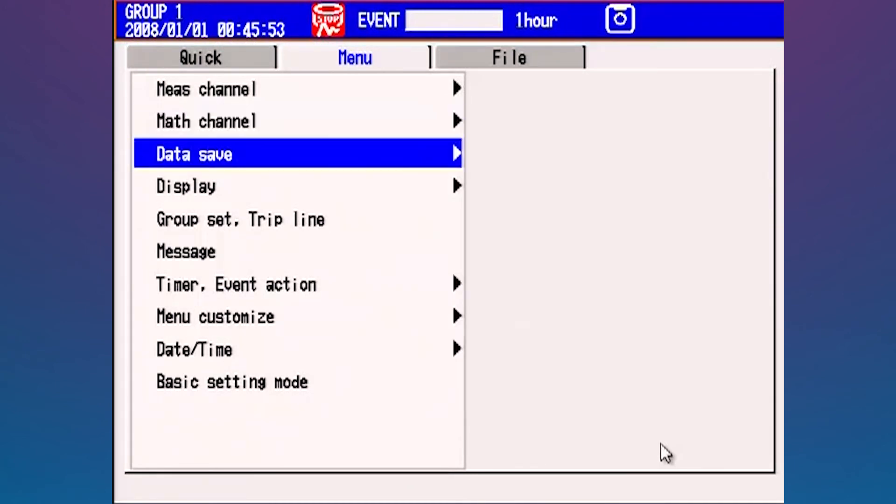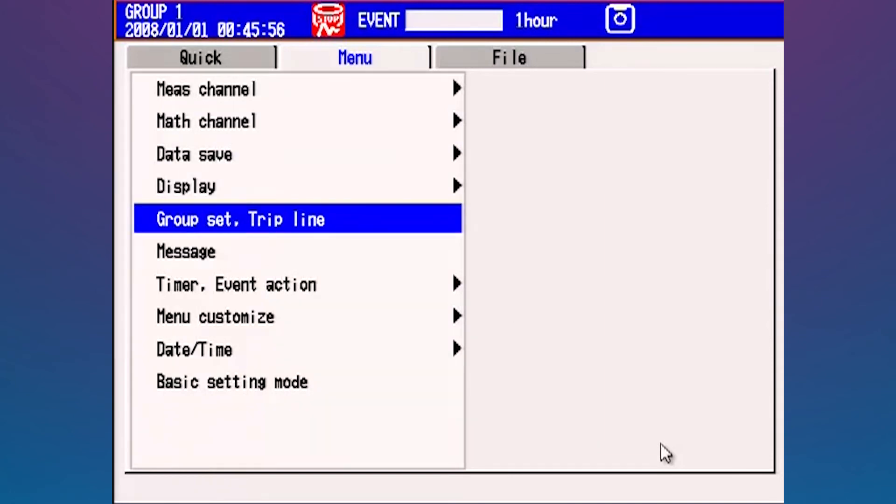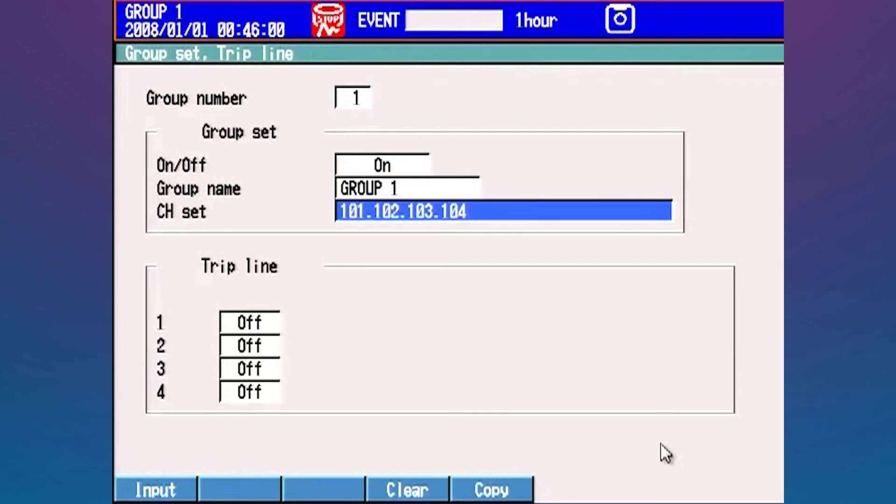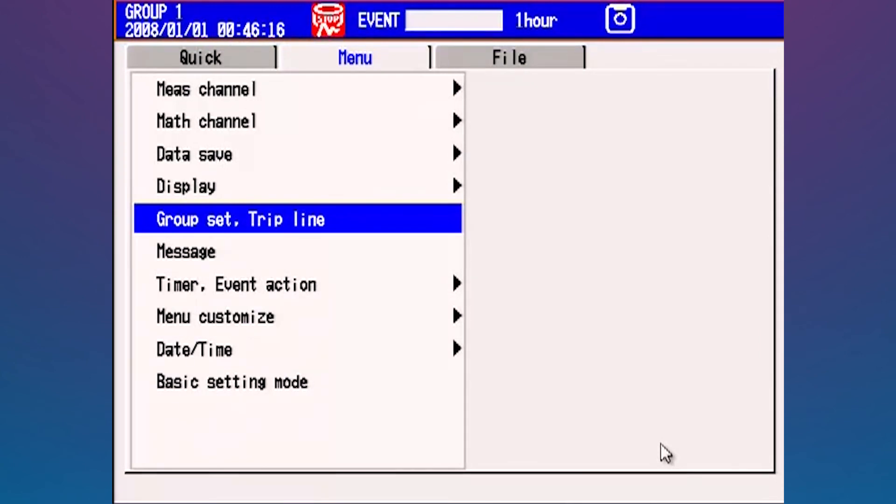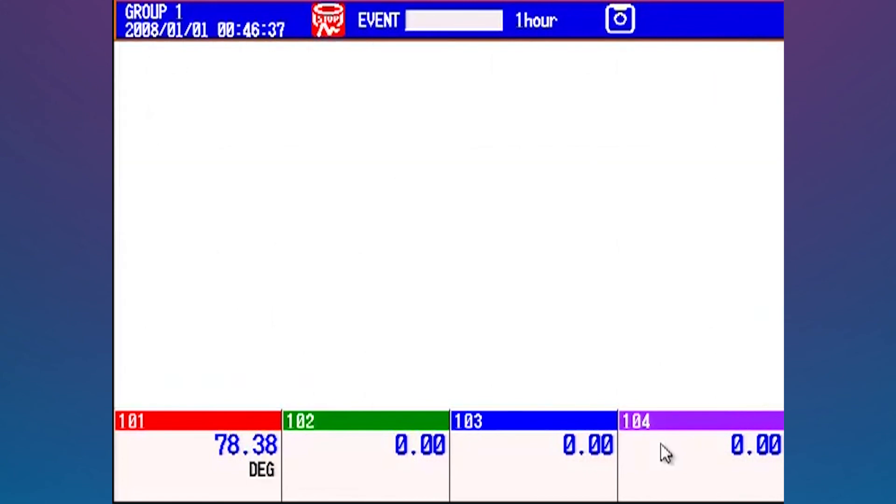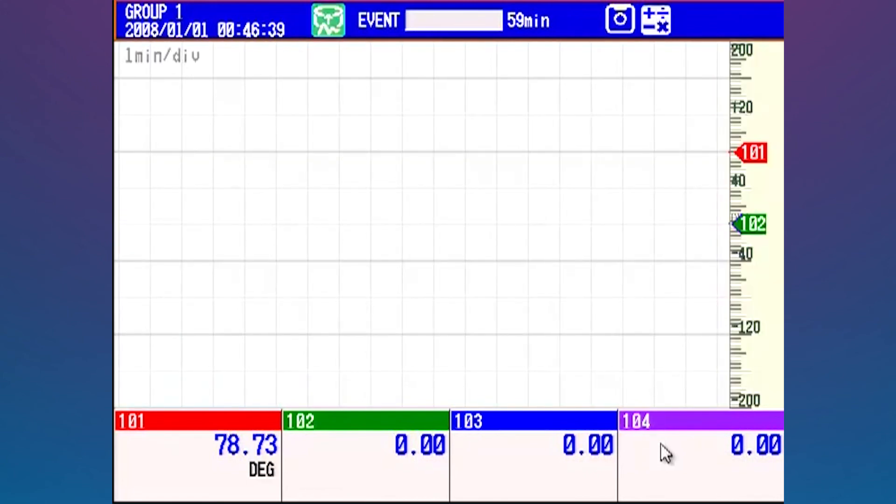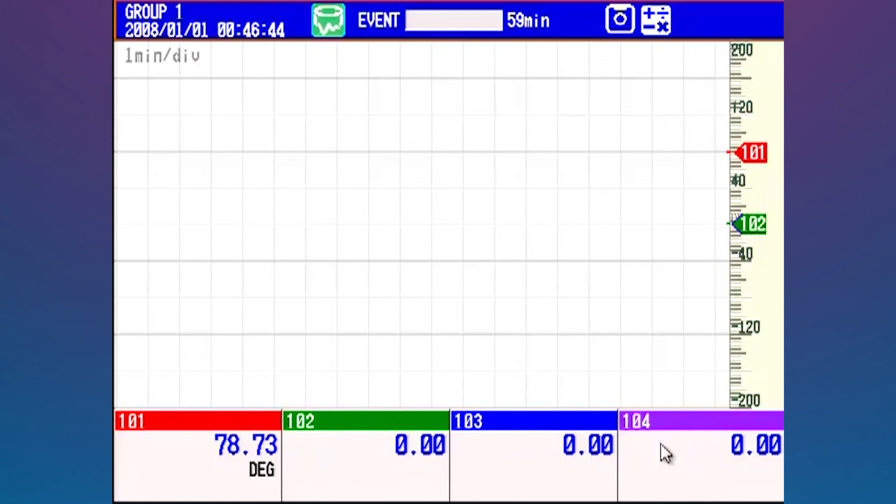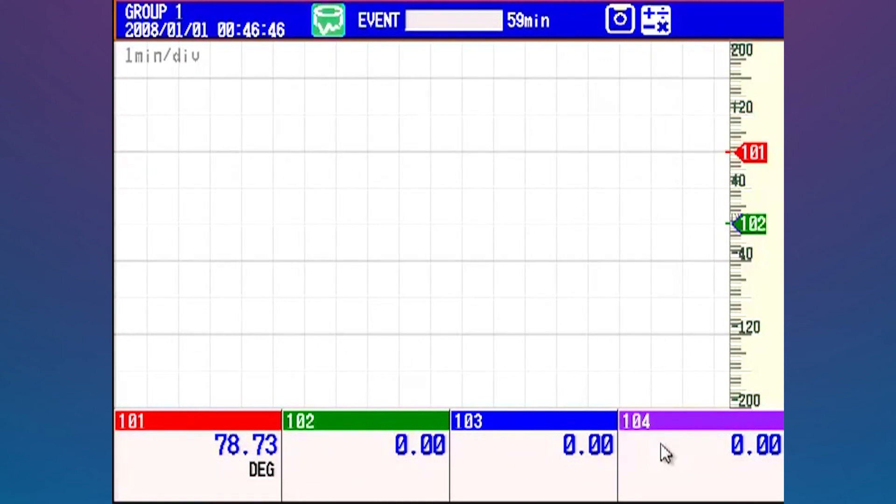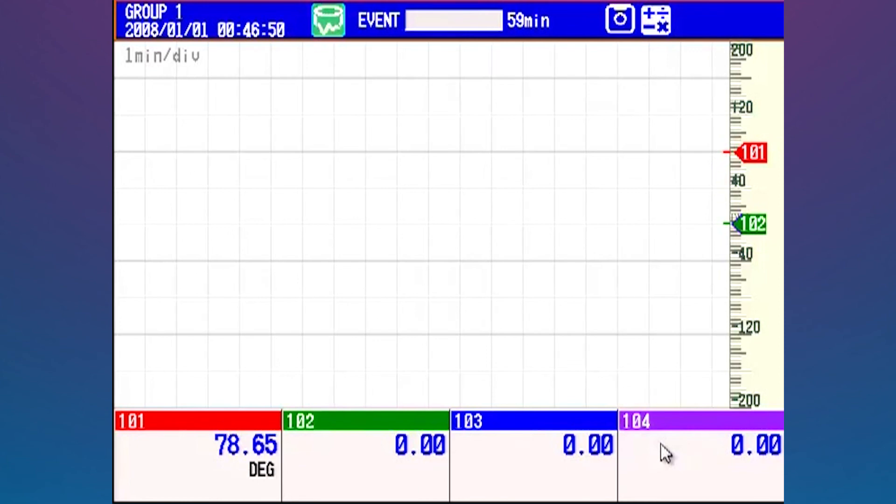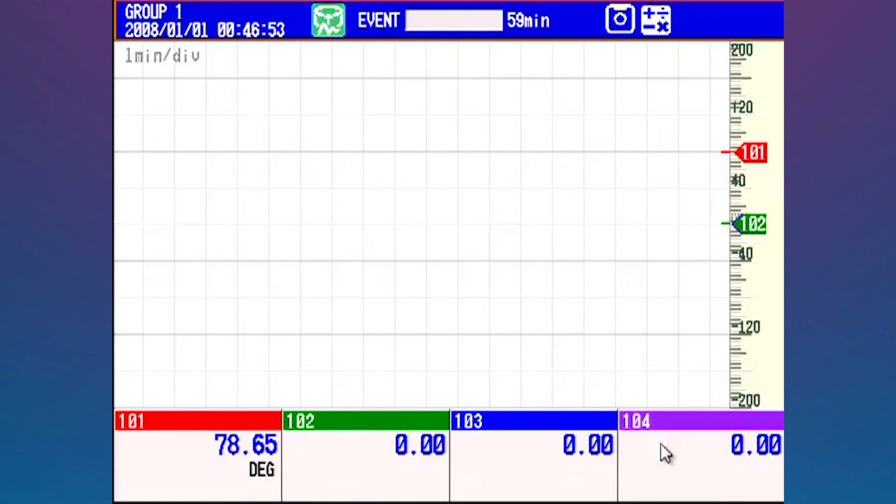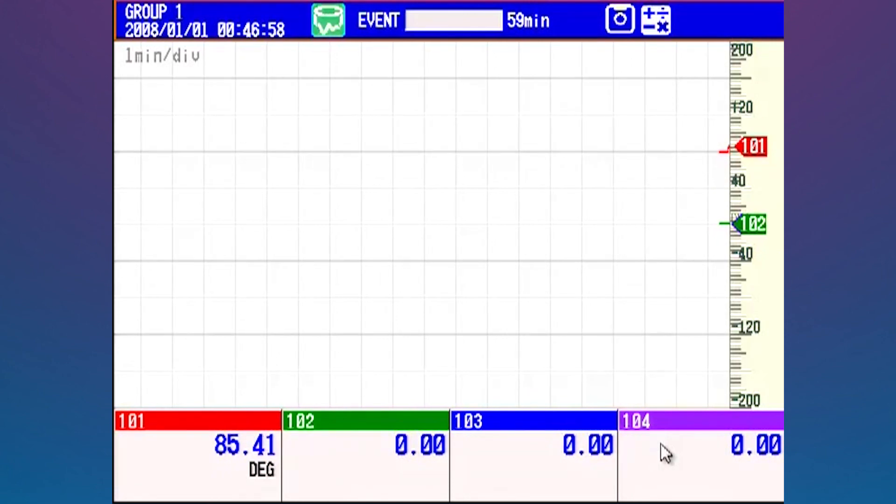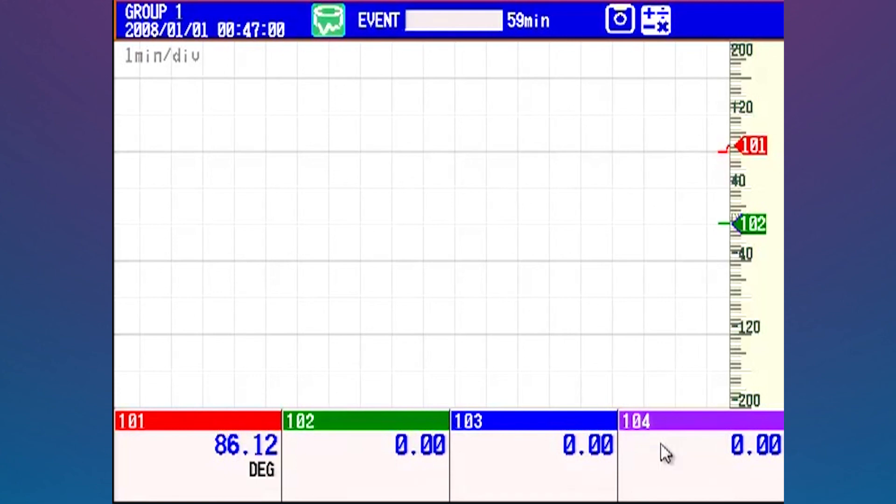The other thing that you're going to need to do is go down here and go to your group set. Once you've set up all your math channels, you're going to want to put them in a group. In this case, I've gone ahead and built a group and you can see I've put in the 101, 102, 103, 104 as my group, and then hit display enter to accept that change. Hit escape to back out, escape to back out again. We can see here I'm actually looking at group one. One thing you're going to notice is that temperature is not actually changing there, and the reason it's not changing is because I haven't started my math or recording yet. So I'm going to go ahead and hit the start stop button. There we go. I've got the start and we can now see that it's up, it's running, and that's 78.73. You can see how it's kind of moving around a little bit. That means it's pulling that data directly from the MW100.